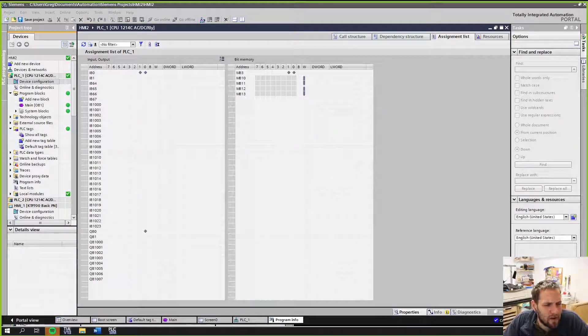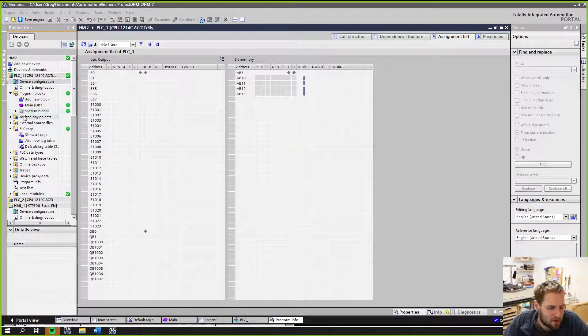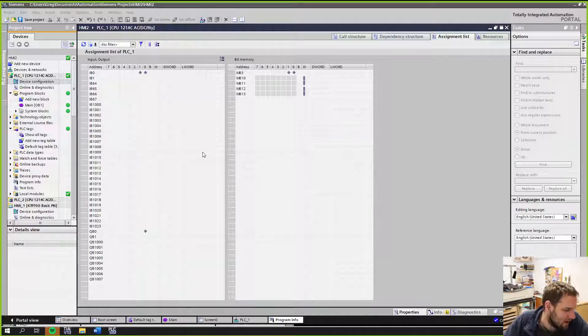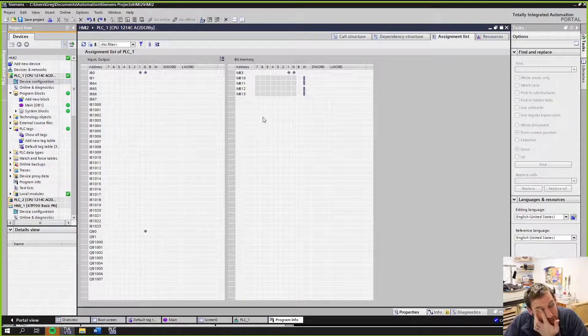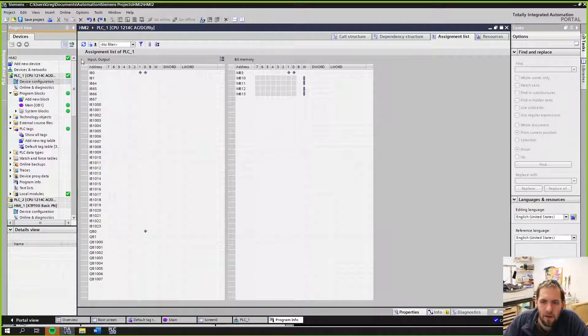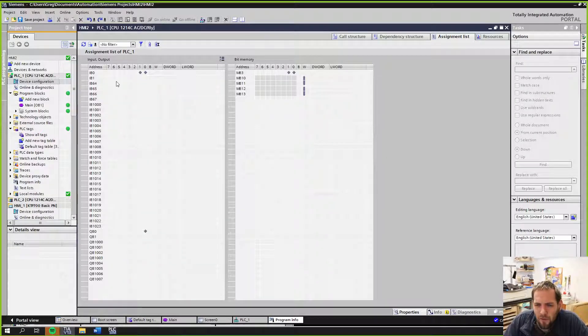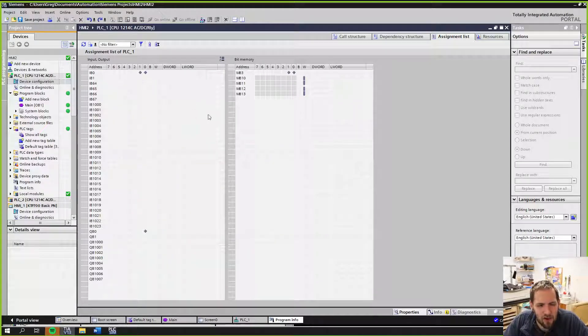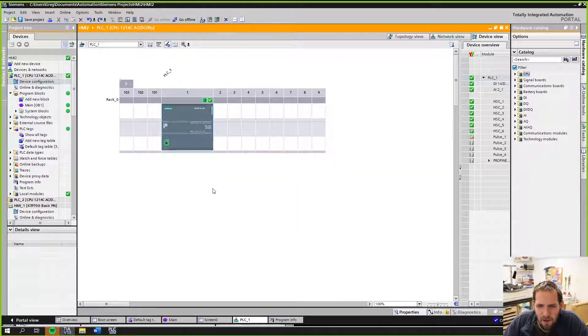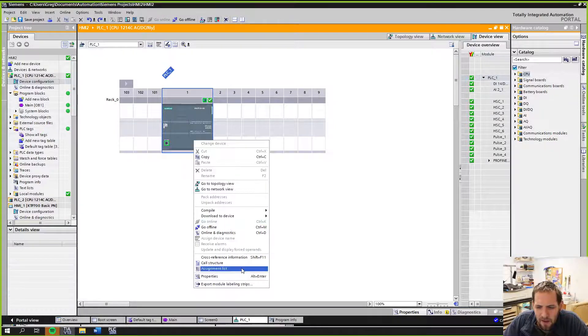We've already talked briefly about our different data types — integers, short ints, booleans, and we've kind of hit up double ints and reals. But the main things we've been dealing with so far are booleans. What I've brought up here is the assignment list. This shows you the location of every tag that you've used in your program. If you create a tag but don't actually use it, it doesn't show up here. I got here by going to device configuration, right-clicking on the PLC, and selecting assignment list.